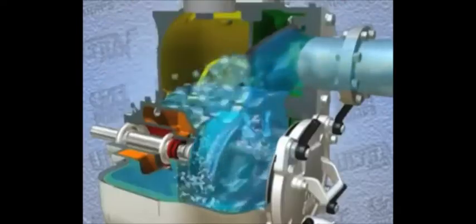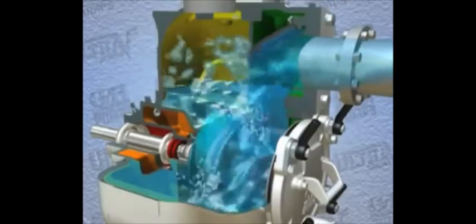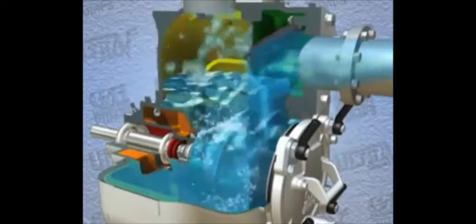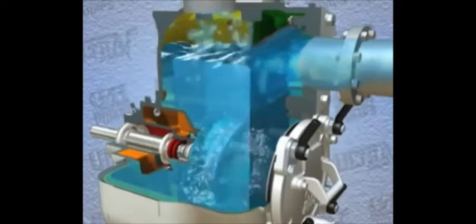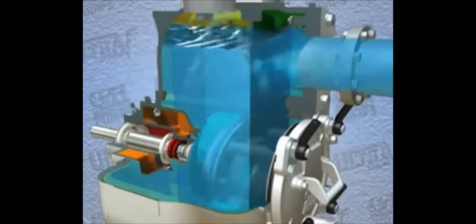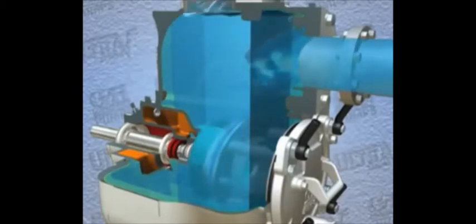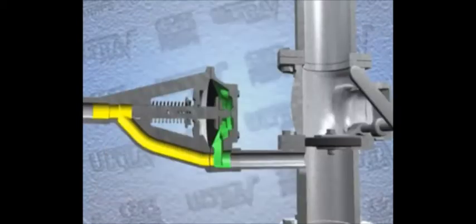Differential pressure causes the liquid to rise in the suction line until dynamic operation is achieved. This is achieved without the need for external priming devices or foot valves, which add to owner maintenance and increase the potential for costly repairs.